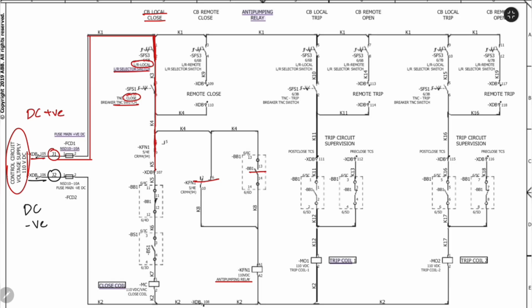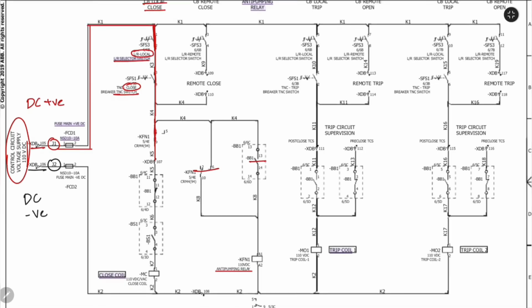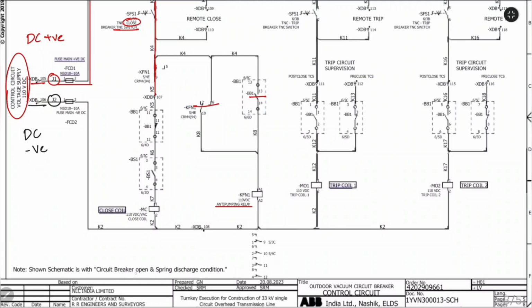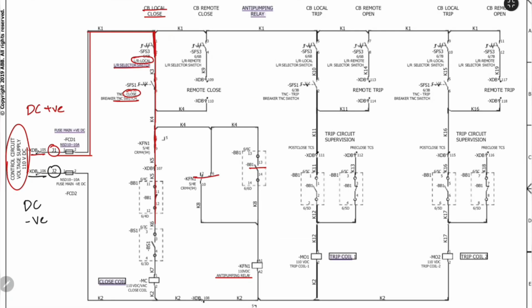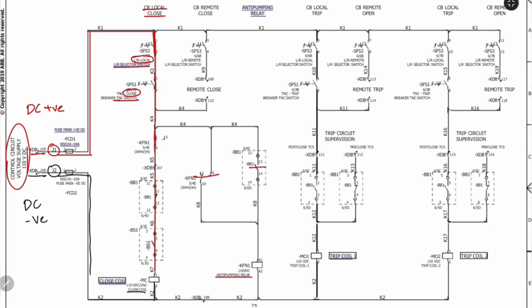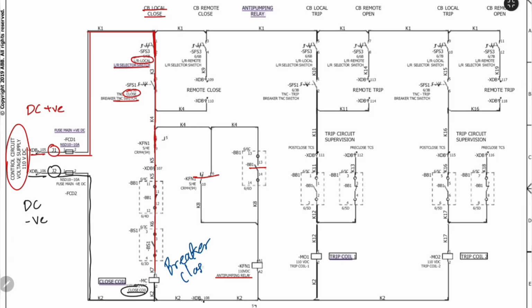Next, the circuit checks the breaker auxiliary contact BB1. Because the breaker is currently open, the normally closed auxiliary contact remains closed, allowing the supply to reach K6. Since the spring was charged earlier, this contact is closed. The DC positive reaches one side of the closing coil, while the DC negative is already connected from J2. The closing coil energizes and the vacuum circuit breaker closes.